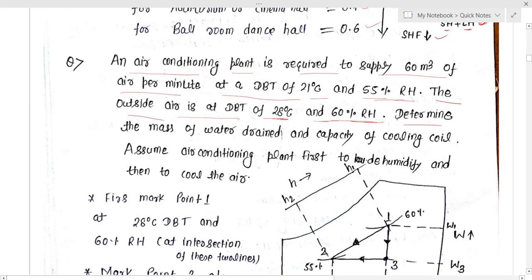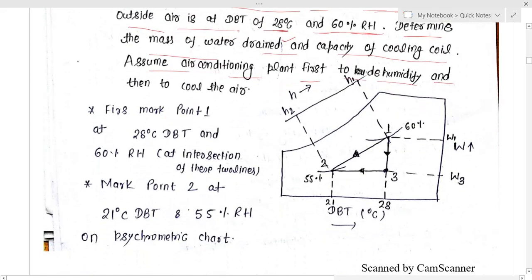We need to determine the mass of water drained and the capacity of the cooling coil. Assume the air conditioning plant first dehumidifies and then cools the air. To solve this, you need a psychrometric chart. First, mark point 1 on the chart at 28 degree centigrade dry bulb temperature and 60% relative humidity.